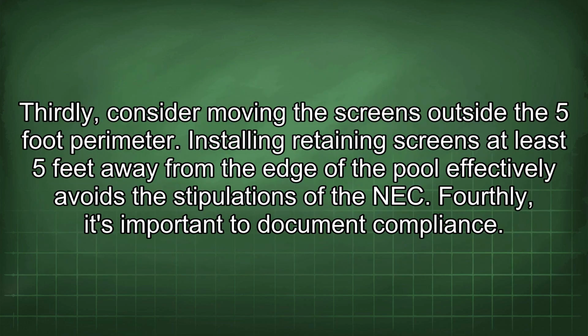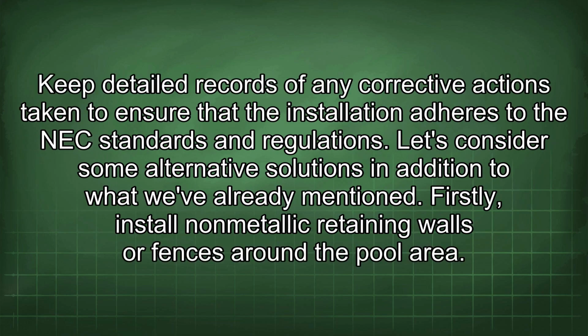Thirdly, consider moving the screens outside the 5-foot perimeter. Installing retaining screens at least 5 feet away from the edge of the pool effectively avoids the stipulations of the NEC. Fourthly, it's important to document compliance. Keep detailed records of any corrective actions taken to ensure that the installation adheres to the NEC standards and regulations. Let's consider some alternative solutions in addition to what we've already mentioned.